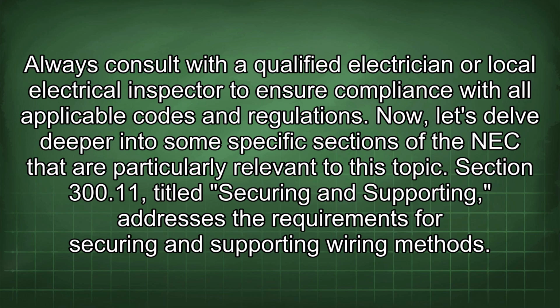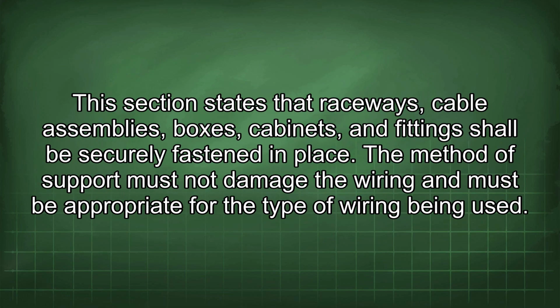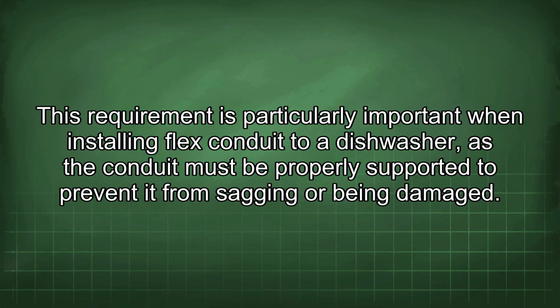Now let's delve deeper into some specific sections of the NEC that are particularly relevant to this topic. Section 300.11, titled Securing and Supporting, addresses the requirements for securing and supporting wiring methods. This section states that raceways, cable assemblies, boxes, cabinets, and fittings shall be securely fastened in place. The method of support must not damage the wiring and must be appropriate for the type of wiring being used. This requirement is particularly important when installing flex conduit to a dishwasher, as the conduit must be properly supported to prevent it from sagging or being damaged.